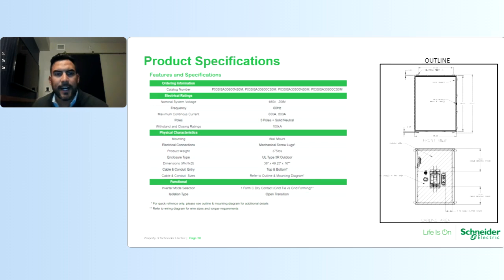So product specs, this is a NEMA 3R device. So it can be installed outdoors, line of sight of the energy storage system. It's available in 4 SKUs. We have this available in 480 and 208 volts, 600 and 800 amps, and has a withstand closing rating of 100 kA. This can be wall mounted. This could be placed indoors next to the main switchboard, wherever you have space in your facility. It's relatively small, and those are the dimensions there. I think we're looking at about 36 inches in width, about 50 inches in height, and about 16 inches in depth. So relatively small product.